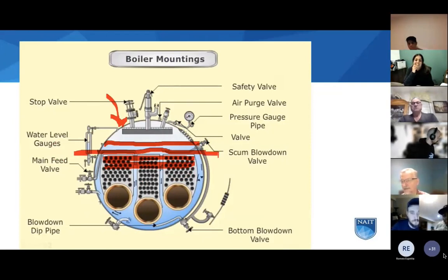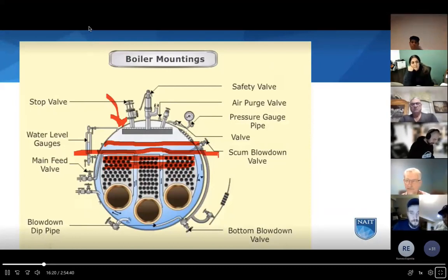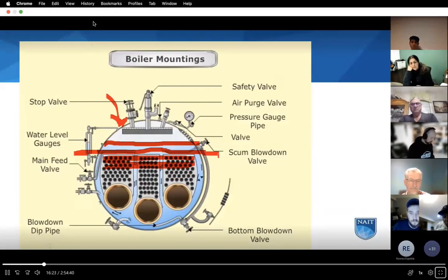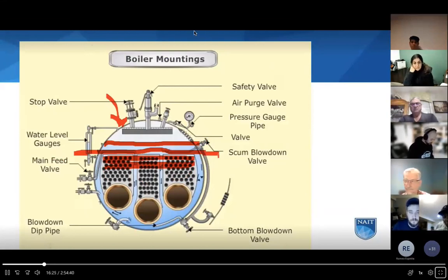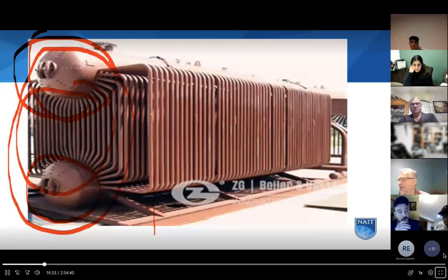In the video we saw where the boiler exploded, it blew an end off of the boiler, or the boiler was propelled out through the wall of the building and moved 30 meters. This is probably a 30 or 40 ton boiler, a medium-sized fire tube boiler. Moving that thing through a wall and another 30 meters is quite the explosion. So extremely lucky that people were not killed.